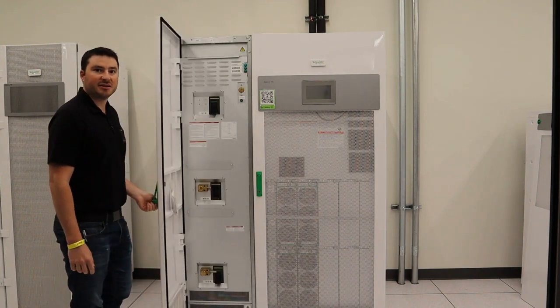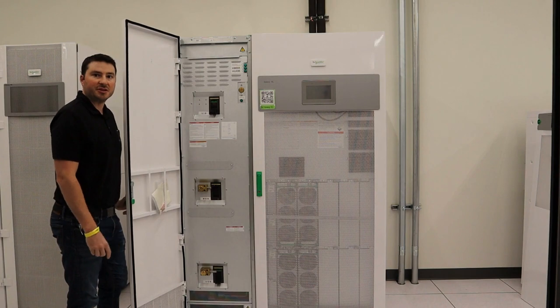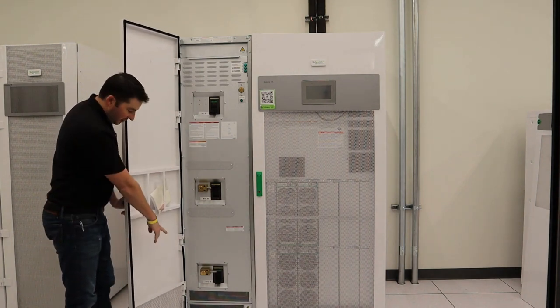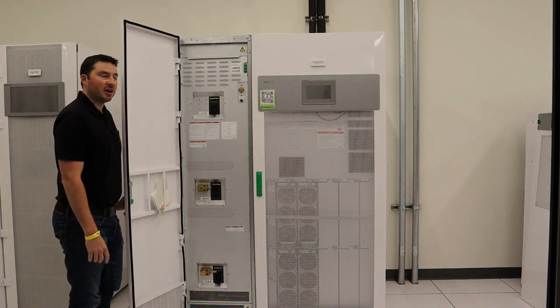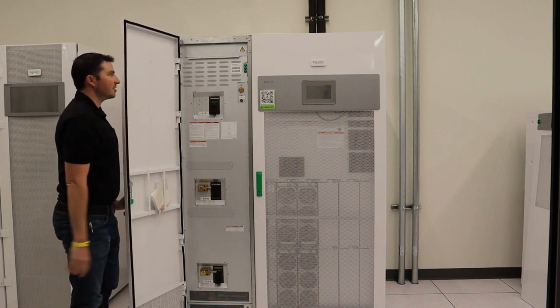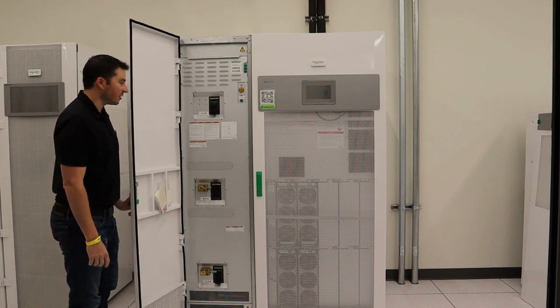This first cabinet is the maintenance bypass cabinet. You have three circuit breakers: UIB or unit input breaker, MBB maintenance bypass breaker, and at the bottom UOB or unit output breaker. Kirk key interlocks the maintenance bypass and the output breaker with the trapped key and the solenoid up here. You have indication lights for the MBB and the UOB unit output breaker.